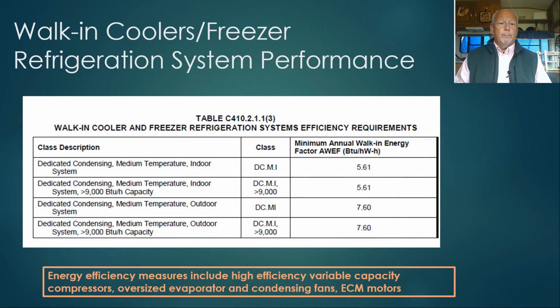For the system performance of the compressor and condensing unit, we also have requirements, and this looks at the performance of the evaporator fans and evaporator coils within the walk-in cooler, and then the condensing unit and the compressor that's external to the walk-in cooler. So there's a new performance criterion called AWEF, the annual walk-in energy factor, and that's a BTUH per watt-hour value. Again, depending on whether you have a dedicated condensing unit, what the temperature is, and whether it's a system located inside or outside the building enclosure, these are the minimum efficiency values. This would be similar to a SEER rating on an air conditioning unit, for example. So this is an annual efficiency value for the compressor, condensing units, and evaporator systems for walk-in coolers and freezers.